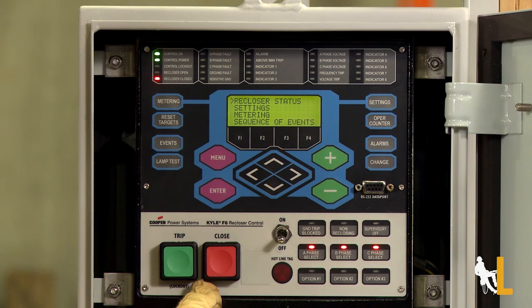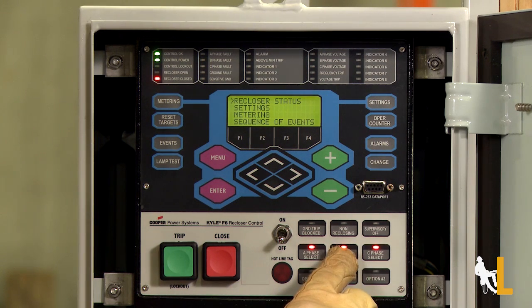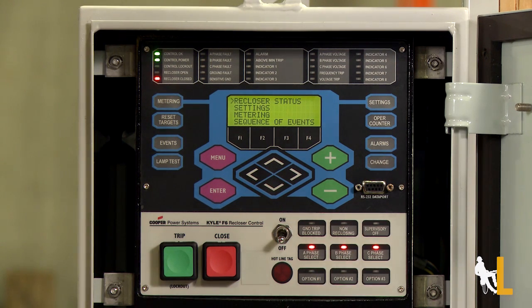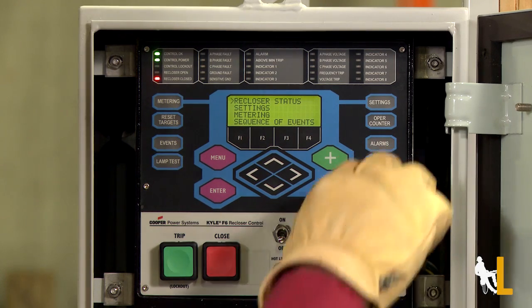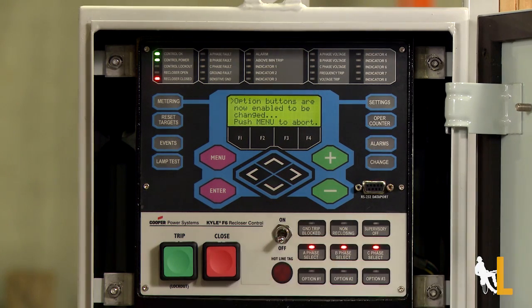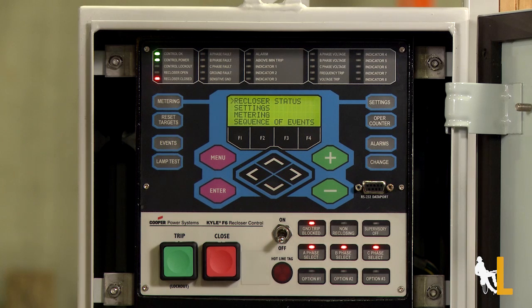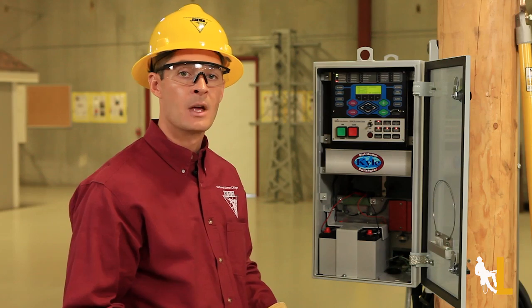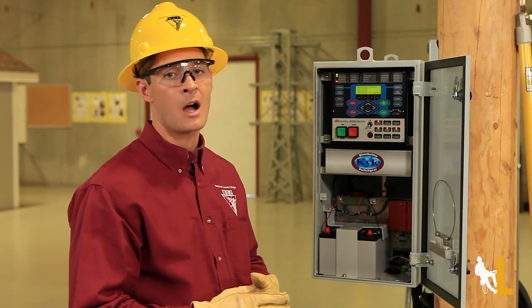These buttons are to open and close the device and over here are the quick access keys. To turn them on or off, first push the change button and then make your selection. Ground trip blocked will disable the ground sensing of the device. Non-reclosing will disable the automatic operation, but it will not change the response time. So if you're doing any hot work, still use the hotline tag.